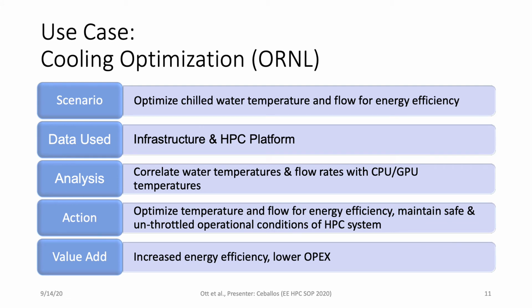The Oak Ridge Leadership Computing Facility at ORNL leverages aggregated data to optimize chilled water temperature and flow for energy efficiency. For the Summit supercomputer, the OLCF currently uses medium temperature water in the secondary loop to minimize the use of chilled water. The use of medium temperature water enables the use of water-side economizers based on evaporative cooling when the weather conditions are advantageous. To further reduce the use of chilled water, especially when the economizers are not efficient, the OLCF uses the aggregated data to optimize the cooling water temperatures and flow rates.